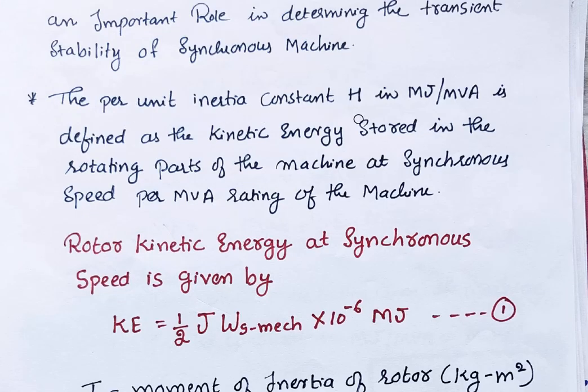The per unit inertia constant H, in Mega Joules per MVA, is defined as the kinetic energy stored in rotating parts of the machine at synchronous speed per MVA rating of the machine. Here we are using the mechanical synchronous speed.